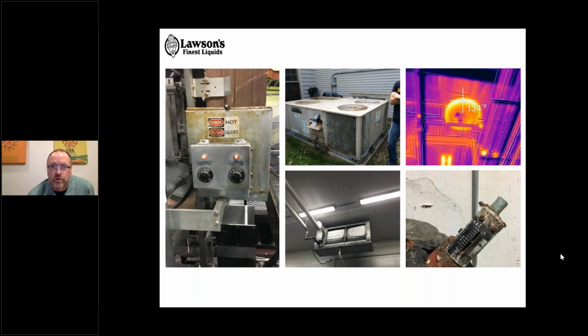Back to the brewery, the thermal picture there was in our dry warehouse. That's a Modine heater, and that's midsummer. It has hot water running through our boiler constantly, 24/7, just dumping heat. The fan's not on, it's not blowing the heat down, it's not calling for heat. So we ended up putting a bypass unit in there, so when it's not calling, it redirects the hot water back into the loop instead of dumping heat onto the floor.